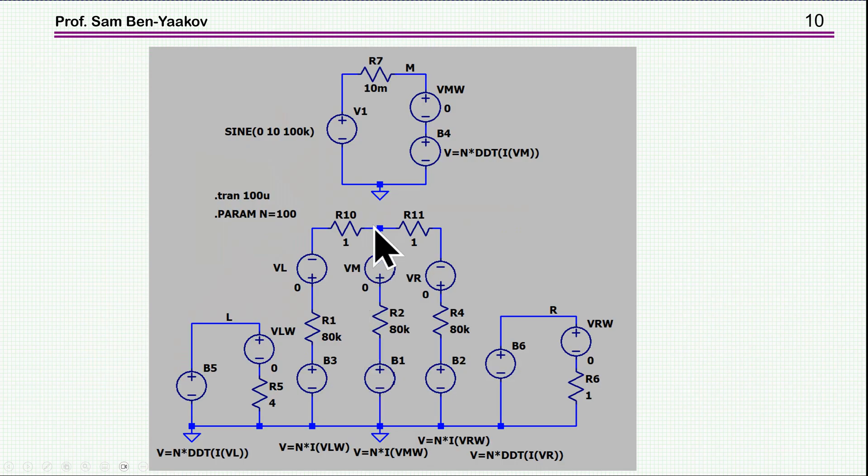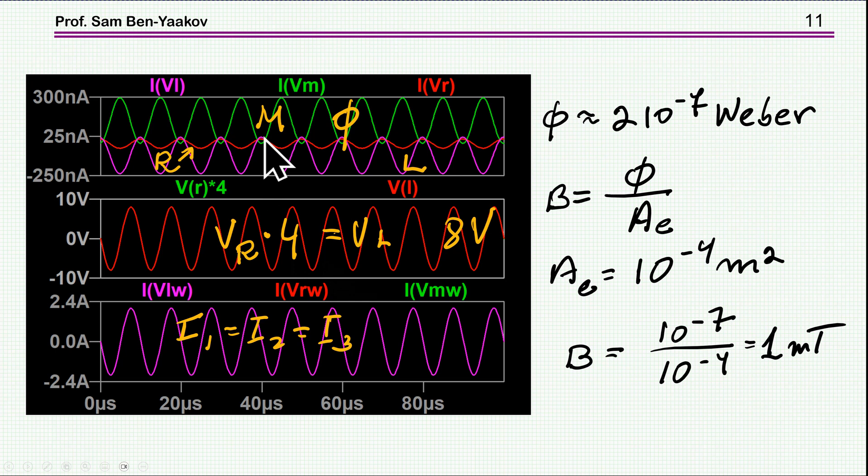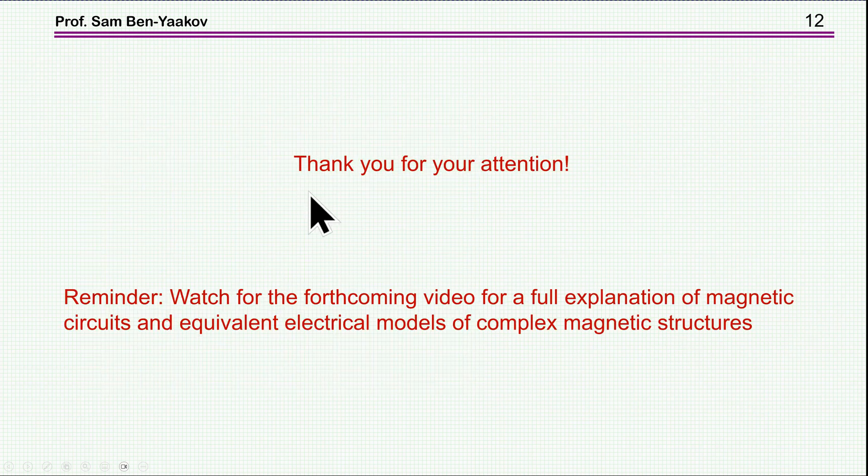So an assumption that the flux of the mid leg is sort of divided equally on each side is just incorrect. So knowing the magnitude of the flux, or the order of magnitude I should say, we can have a notion of what would be the flux density in this particular case. And so the flux density is the flux over the cross section area. And in this particular case it is only one milli tesla. So this is really a core that can sustain a much higher power. This is just an example of course.